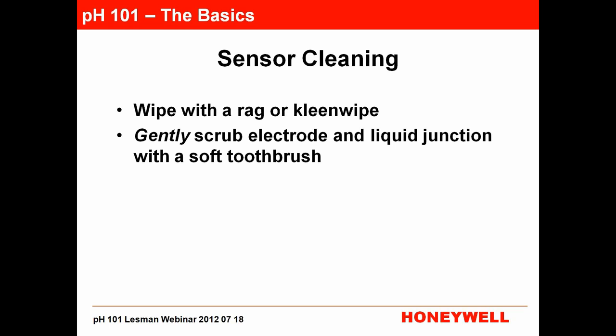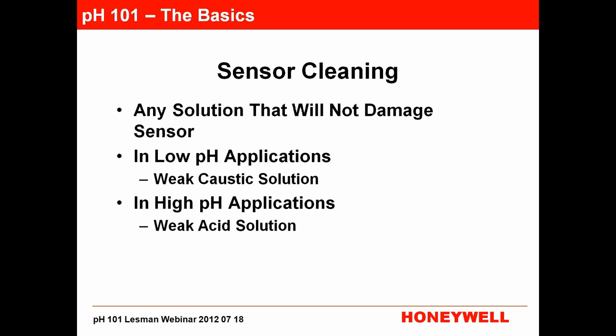There are both chemical and physical cleaning methods for your sensor. For physical cleaning, you can wipe it with a clean rag or wipe, or use a toothbrush. A good rule: don't clean your pH sensor with anything you wouldn't clean your teeth with — so no wire acid brushes. Toothbrushes work great; I always keep one in my tool bag. Use gentle scrubbing and be careful not to break anything.